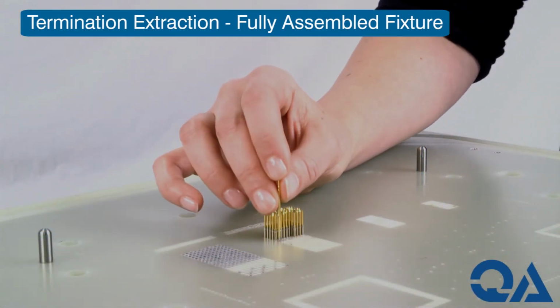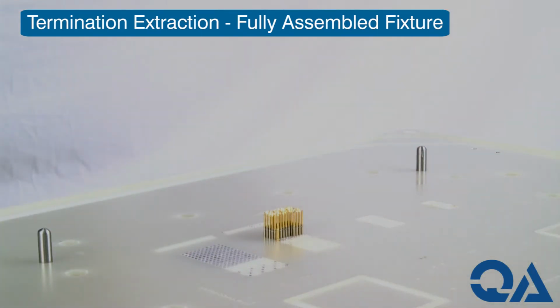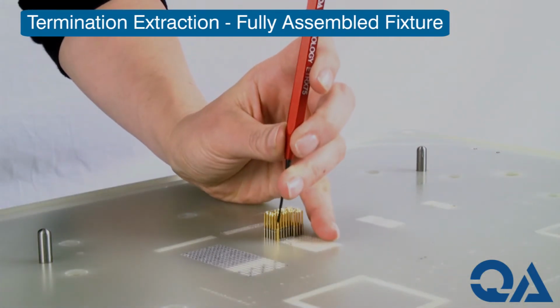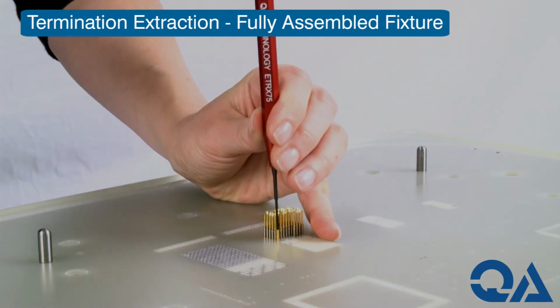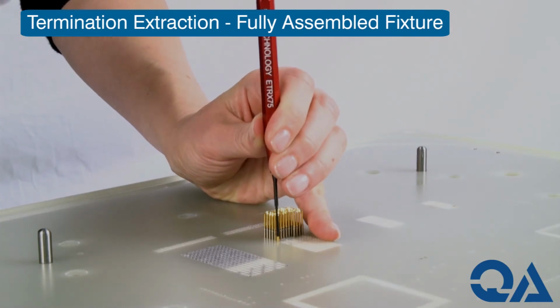To replace the termination pin, drop the replacement termination pin into the probe plate. If the termination pin hangs up in the hole, the extraction tool can be used to push it to its starting position on the top of the back plate.